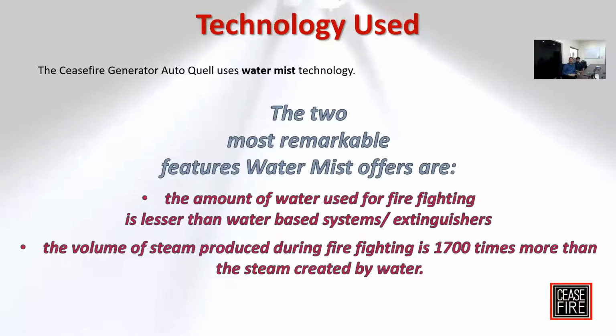We talk about this, and the complete water mist offering is pure and clean. You really don't need to put any foam actually, because water mist itself has enough power to fight any type of fire. So for class B also, without even a foam or with a very little quantity of foam, maybe 0.5% or 1%, you can actually fight any size of fire. That's the beauty of the water mist or atomization technology that we are using.